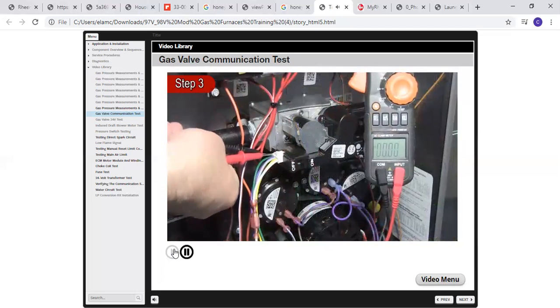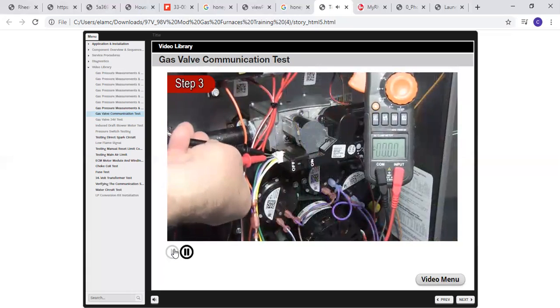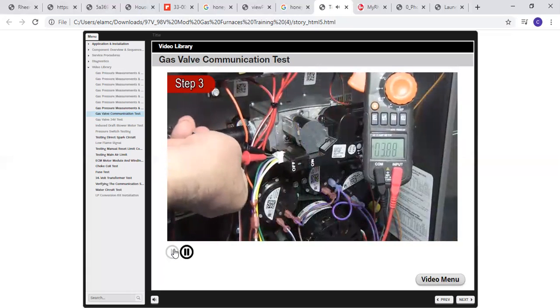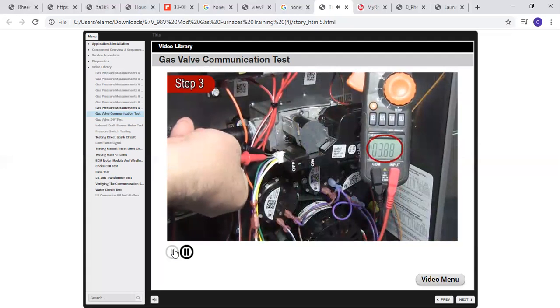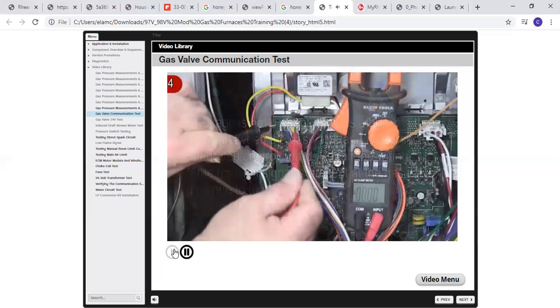Step 3. Check for the transmission signal at the gas valve, purple and green wires. If the transmit signal is present, the gas valve is receiving information from the control board. If voltage is not present, there is a break in the wiring between the gas valve and the furnace integrated control board. Repair the wiring. If the transmit signal is present at the gas valve, continue to the next step.